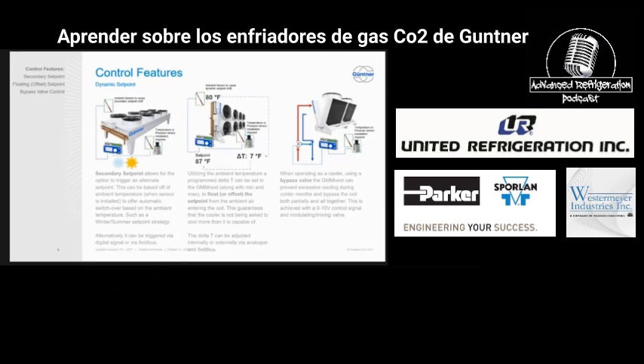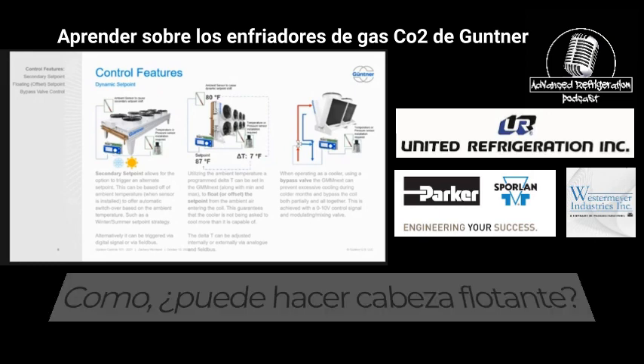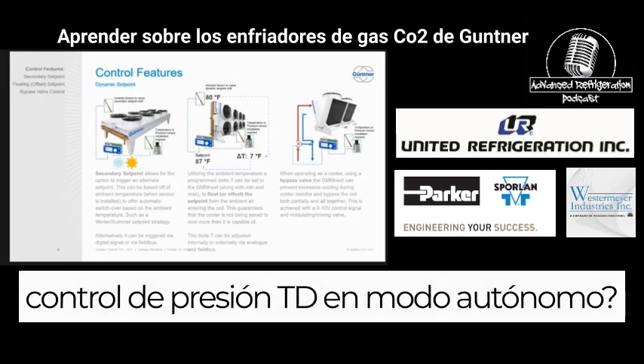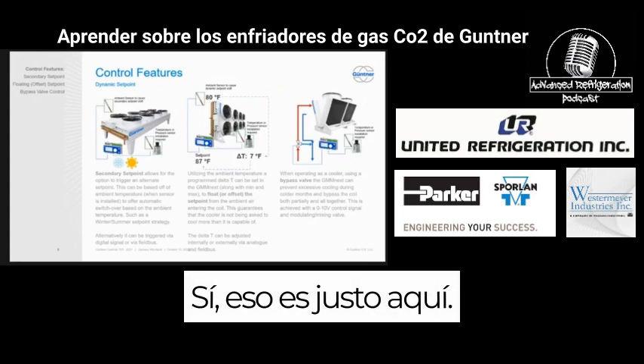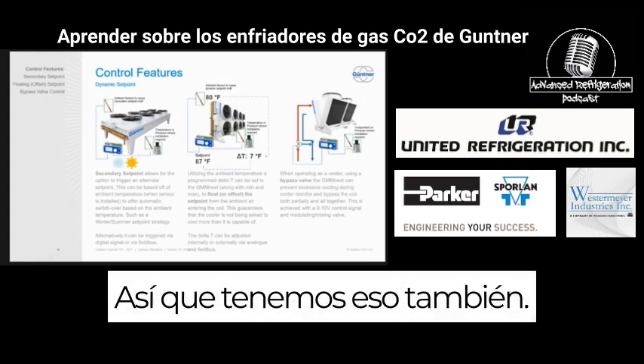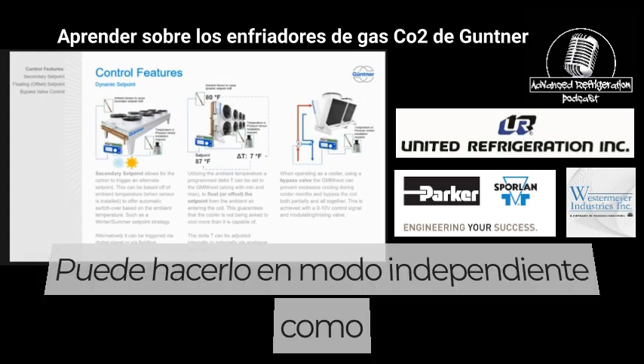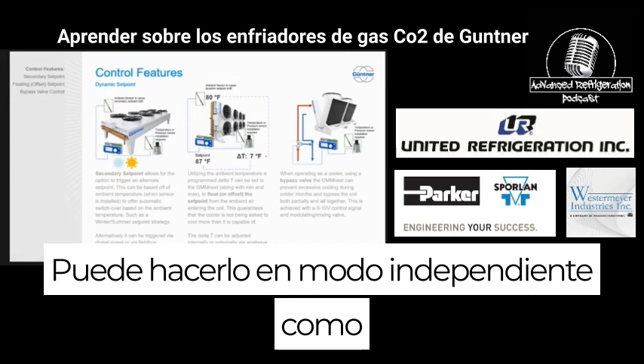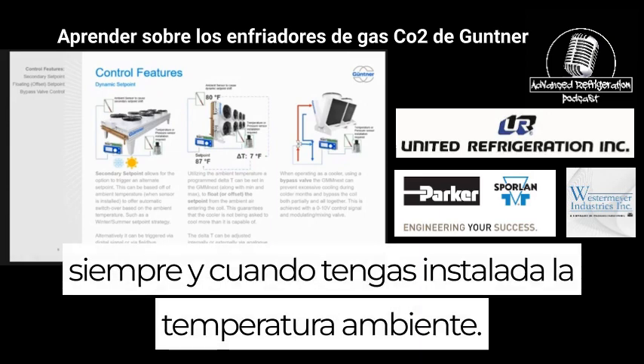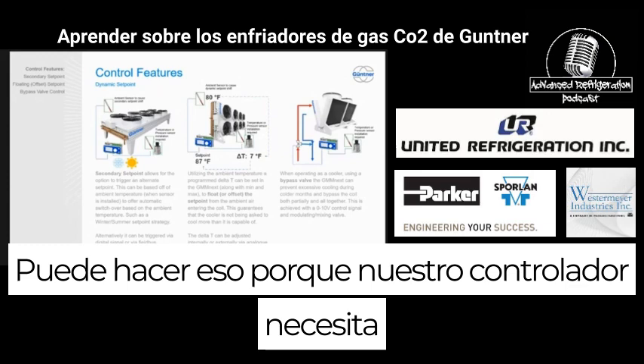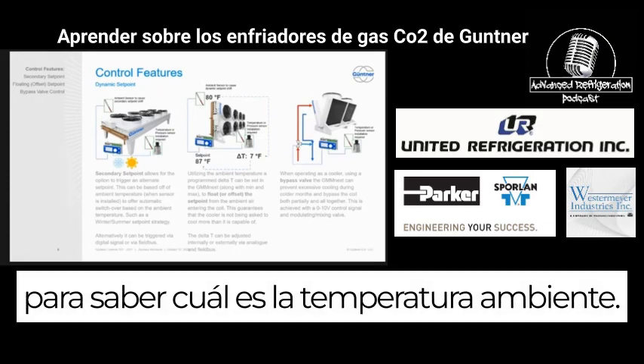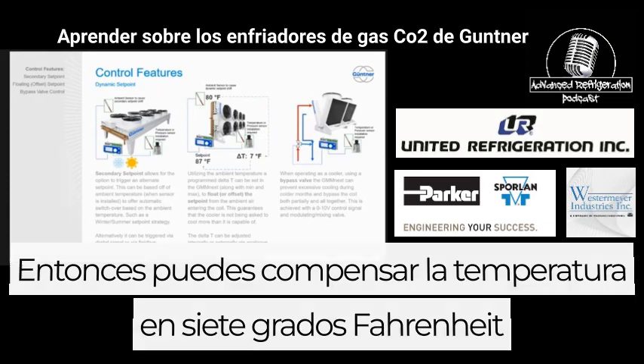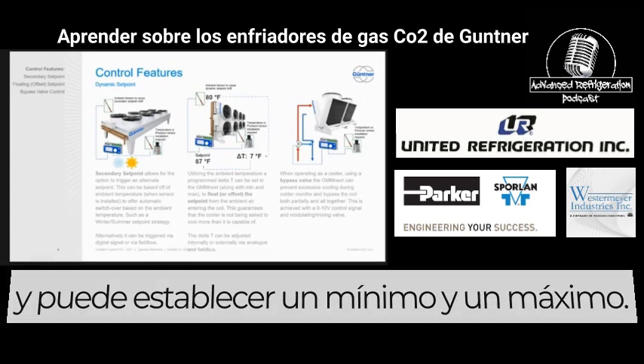So, Will, can it do TD control? Like, can it do floating head pressure TD control in standalone mode? Yep, that's right here. So we have that also. You can do that in standalone mode, as long as you have the ambient temperature installed, because our controller needs to know what the ambient temperature is. So you can offset the temperature by 7 degrees Fahrenheit, and you can set a minimum and a maximum.